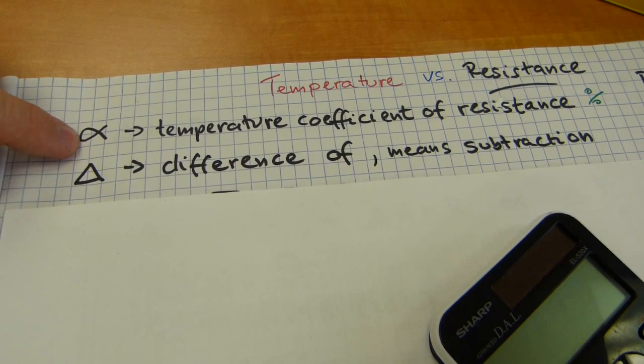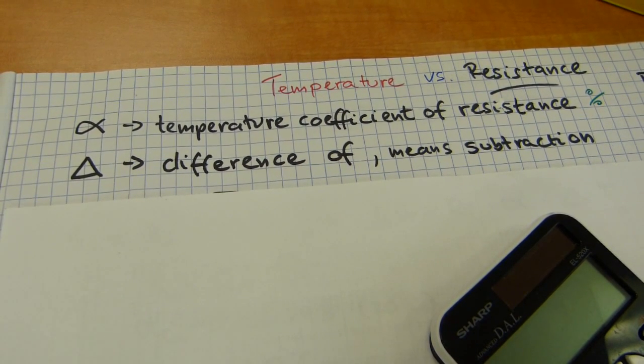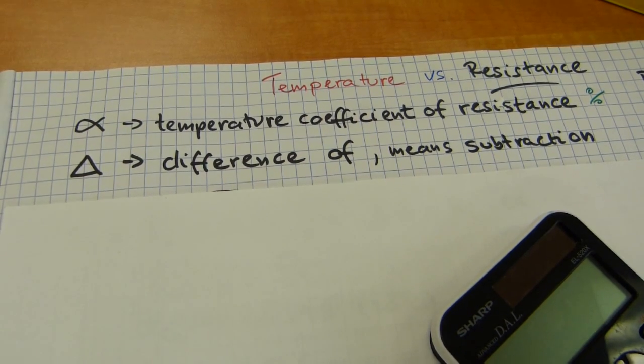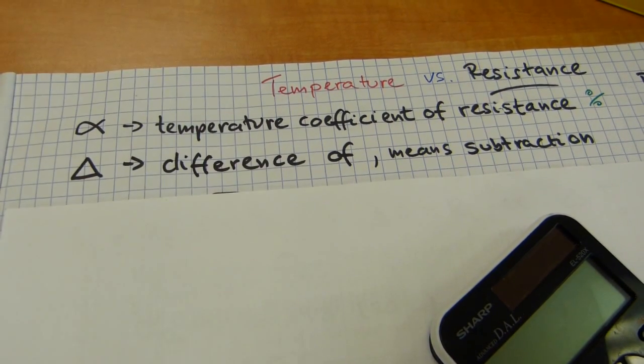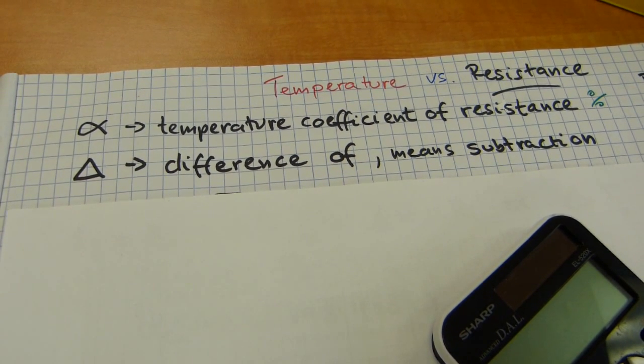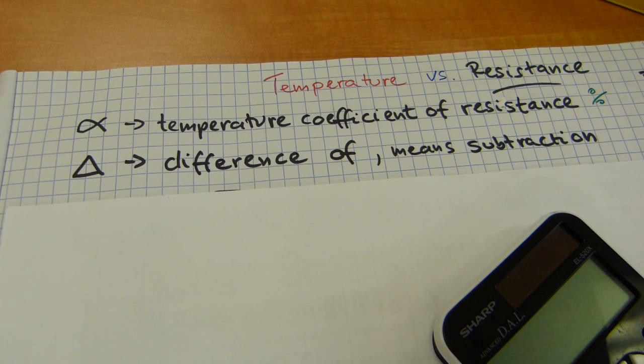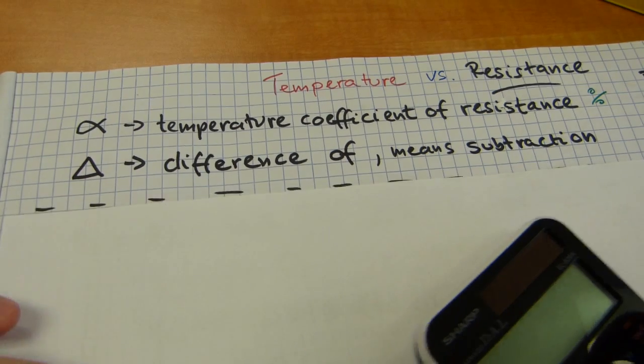However, this alpha number, it does matter. This alpha number of copper is, in this calculation example, relates to Celsius degrees, metric. So even if you're doing, it comes from the North American electrical code, the NEC or the Canadian code or anything North American, both of them are actually working with the alpha number that relates to Celsius degrees. So if you have Fahrenheit, you're going to have to convert that first into Celsius degrees.